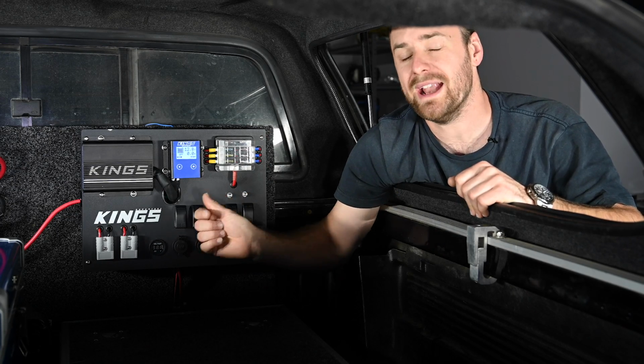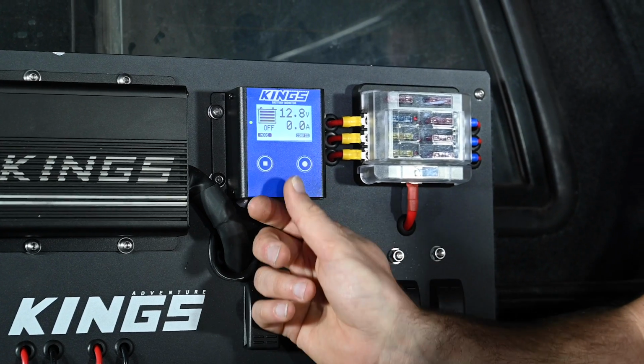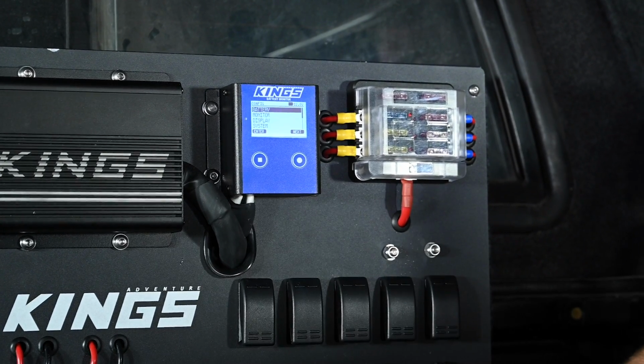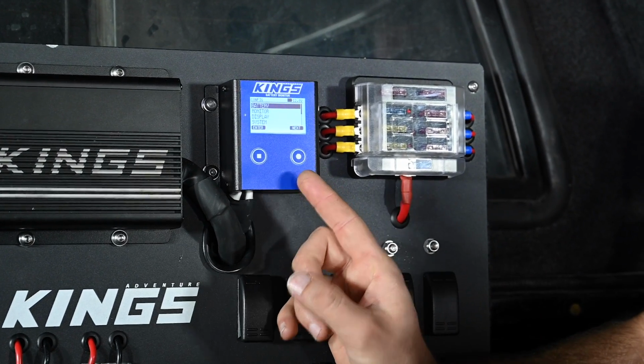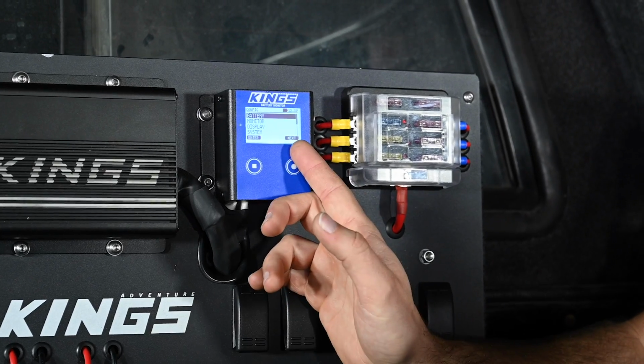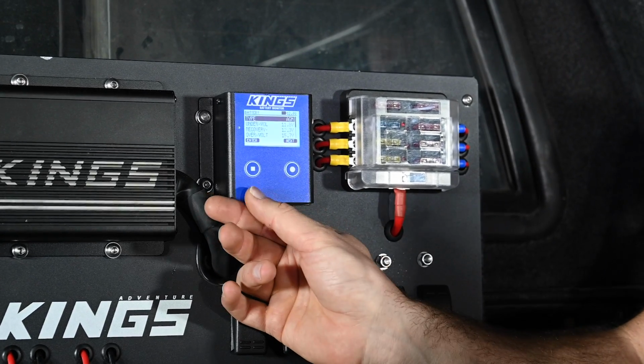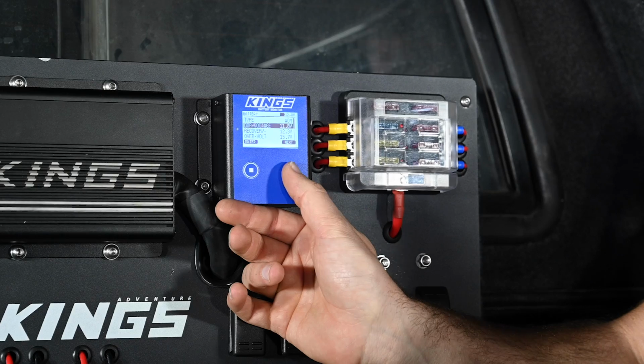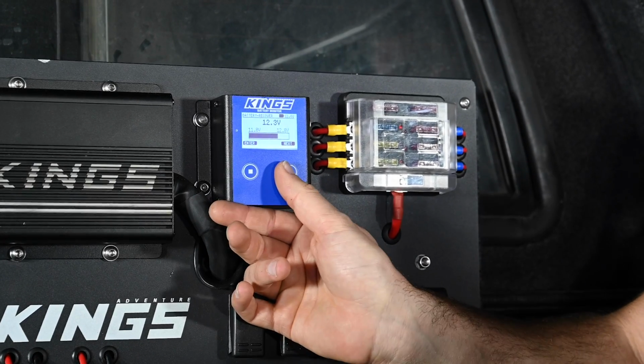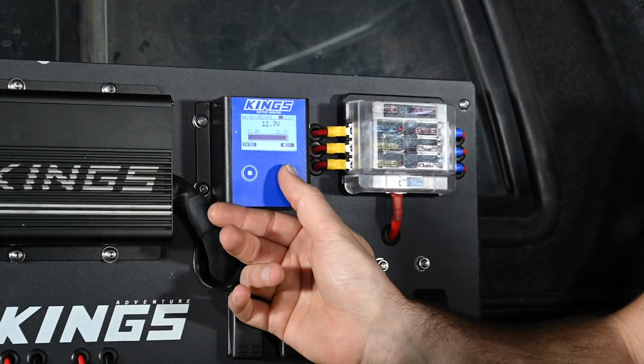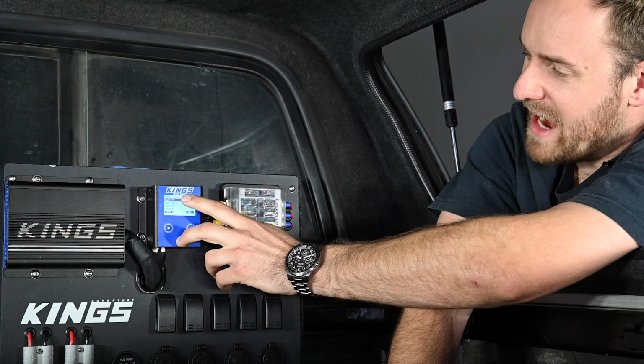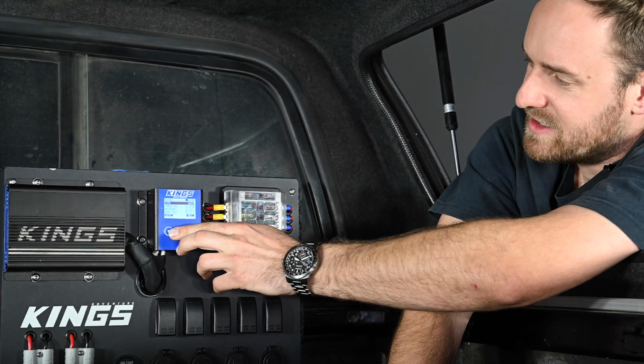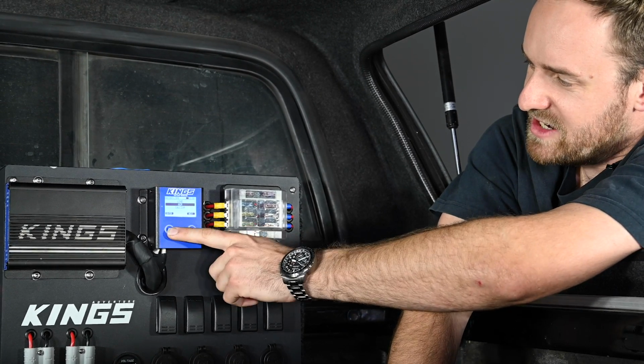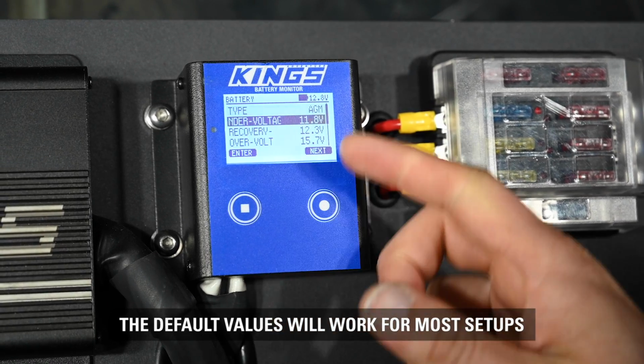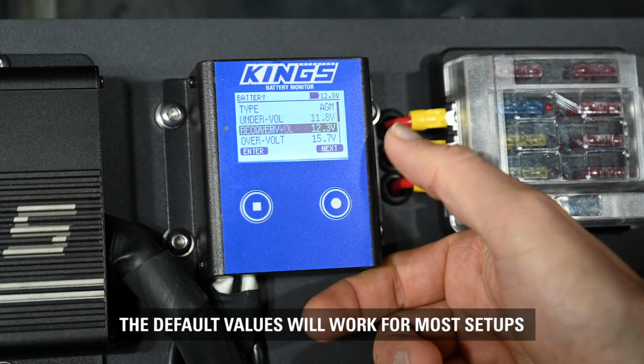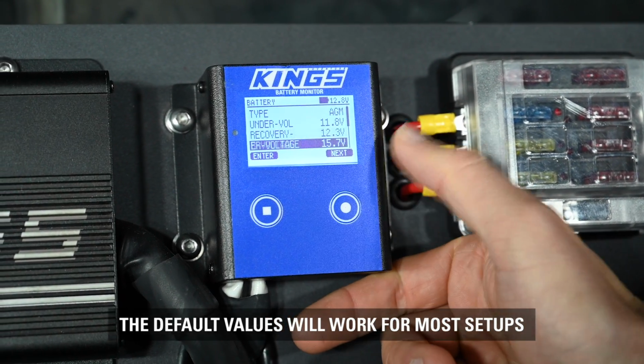First of all, you'll hit the right-hand button, configuration, which brings you into the menu. You'll now notice that the left and right buttons refer to enter and next. Enter obviously goes into the menu, and next will allow you to scroll down or scroll along a particular setting. So first, let's go into battery and then select the type, which in this case is AGM.